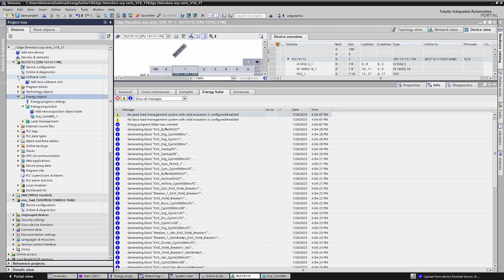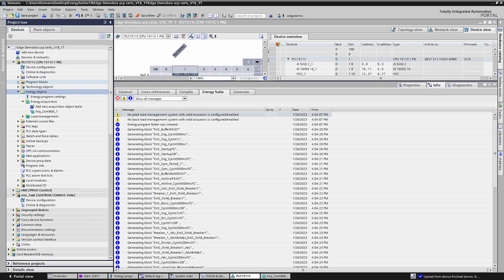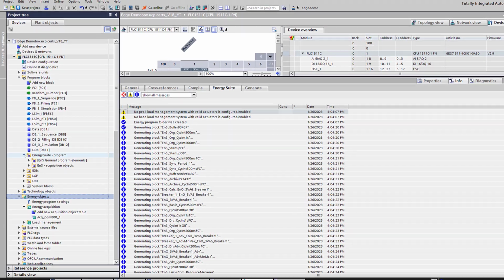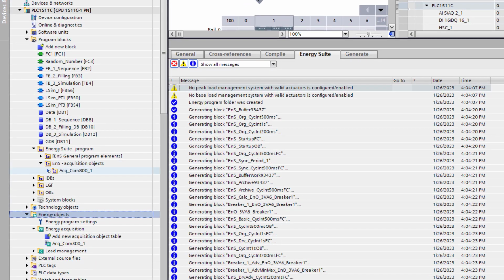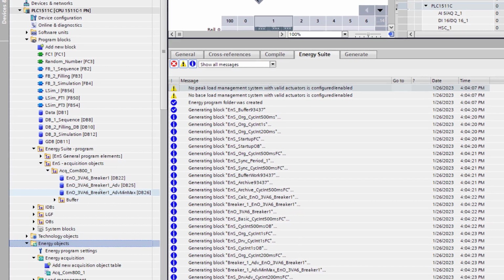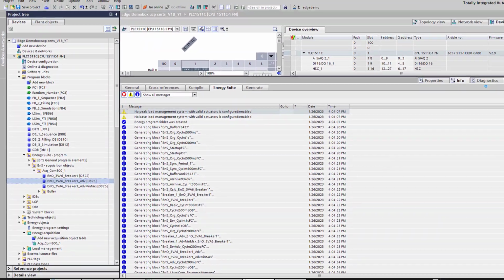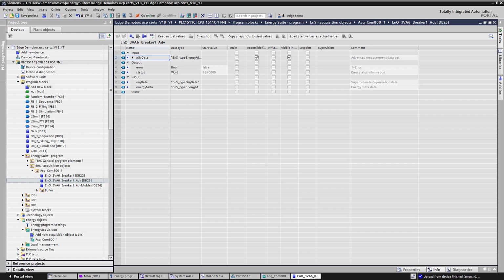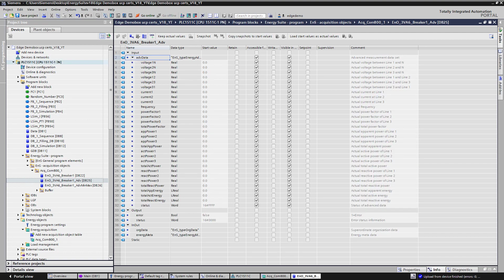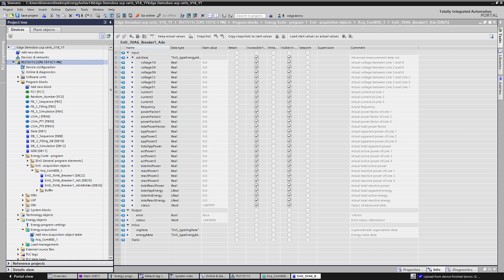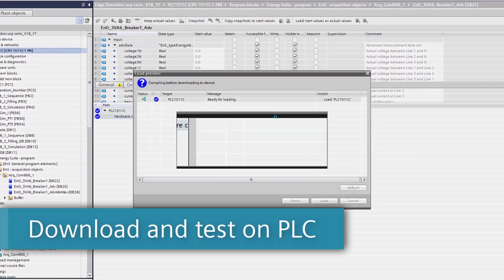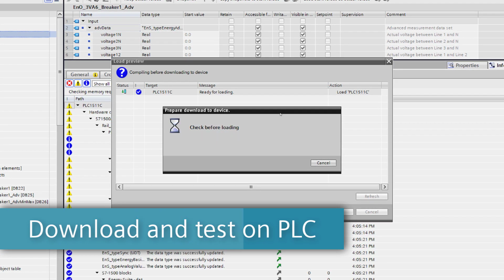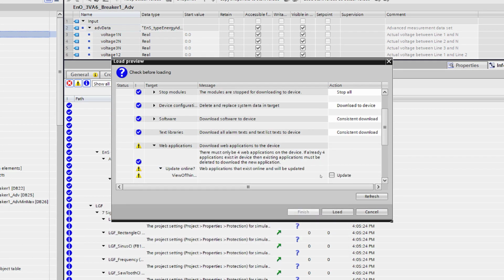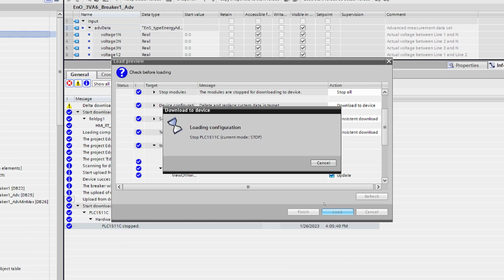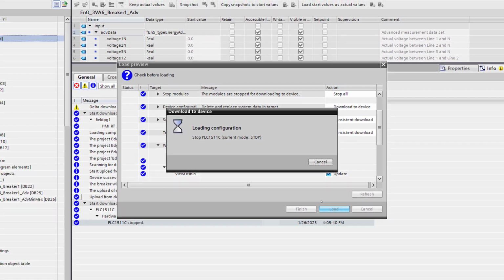Now that we've generated the programming, let's go investigate to see what's there. Under the acquisition objects, we'll find the advanced data block. Within this structure, you'll find the most detailed tags. I'll go ahead and speed things up with the load preview here, or we'll just download to the PLC. We added hardware, so the PLC does go to stop, and we'll start the module.